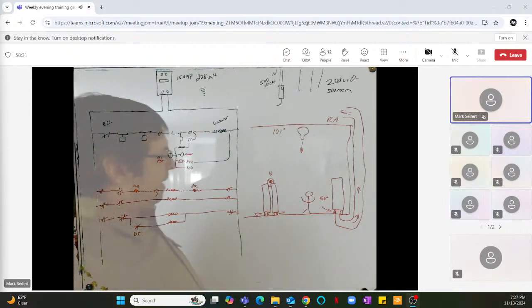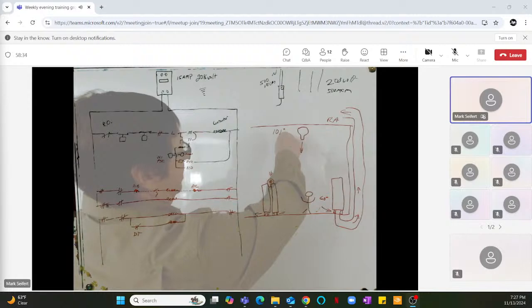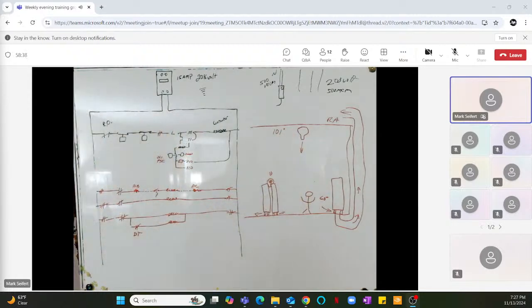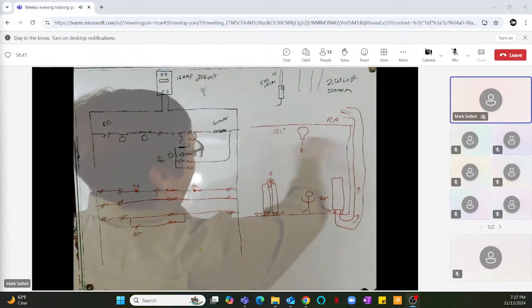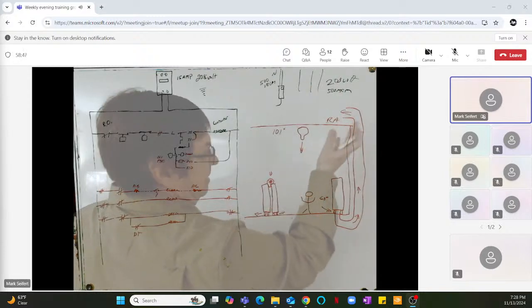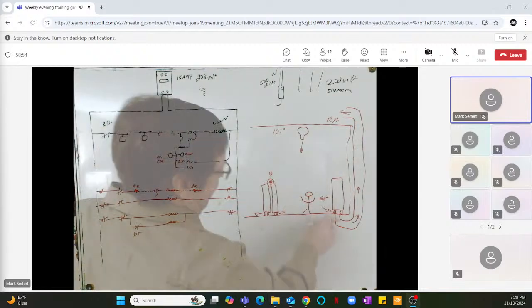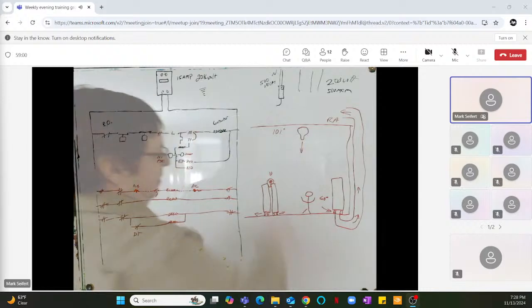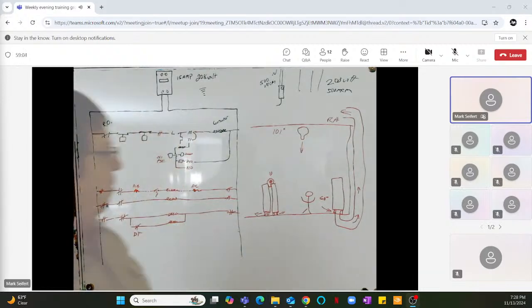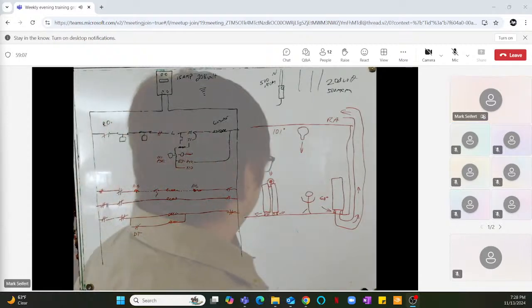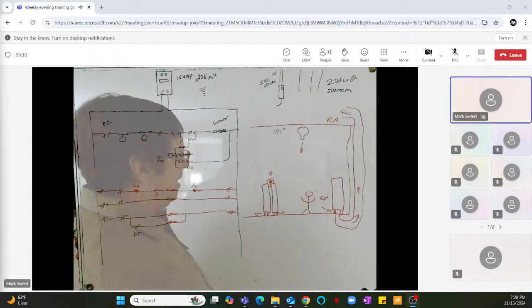And why would we want to do that? Well, because something has to replace that air. Guess what that is? It's the 101 degree air. It's forced to come down, because why is it up high to begin with? Hot air rises, gravity, right? It's expanded. The more compressed molecules are going to sink. But if we can yank them out, our 101 degree air is going to come down and blast everybody with some nice, warm, heat dissipating, heat energizing air.